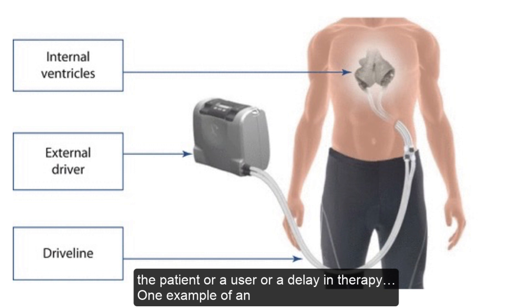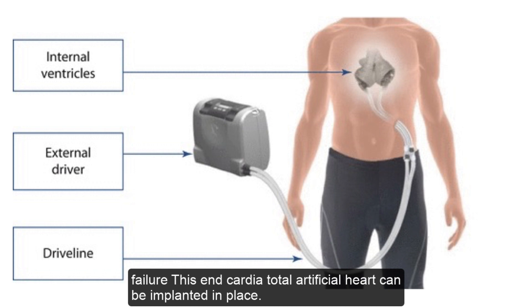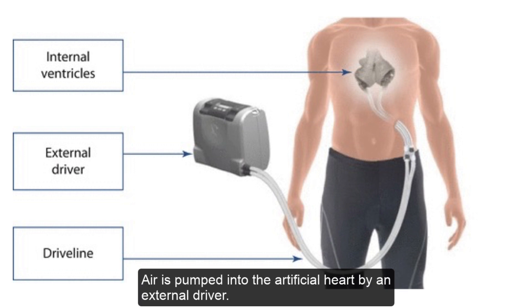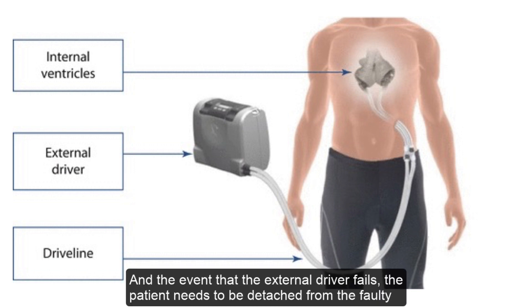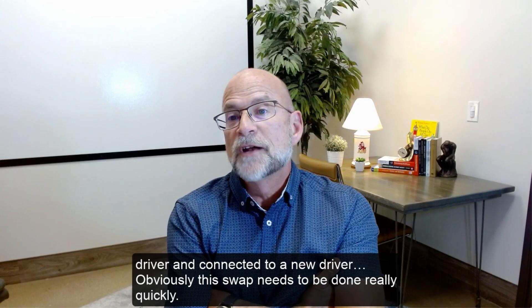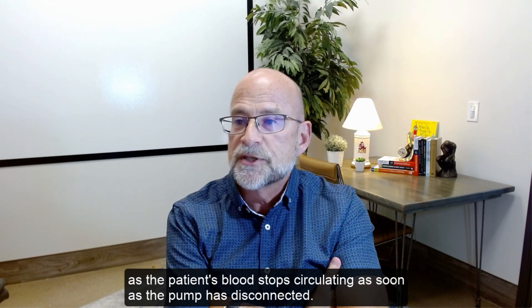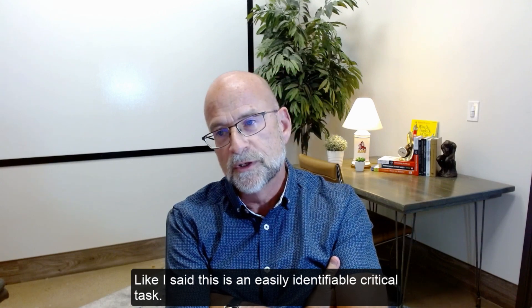One example of an obvious critical task is found in SynCardia's total artificial heart. In the event of complete heart failure, the SynCardia total artificial heart can be implanted in place of the two ventricles as a bridge to transplant. Air is pumped into the artificial heart by an external driver through tubes called drive lines. If the external driver fails, the patient must be detached from the faulty driver and connected to a new one — quickly, as blood stops circulating as soon as the pump is disconnected.